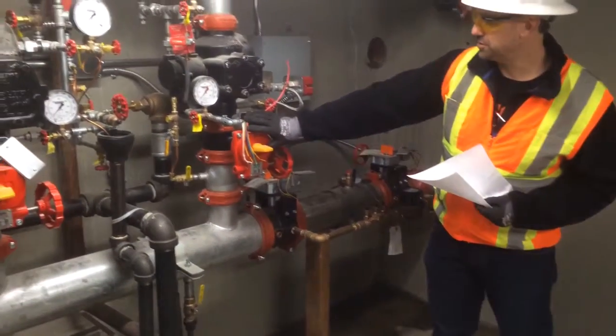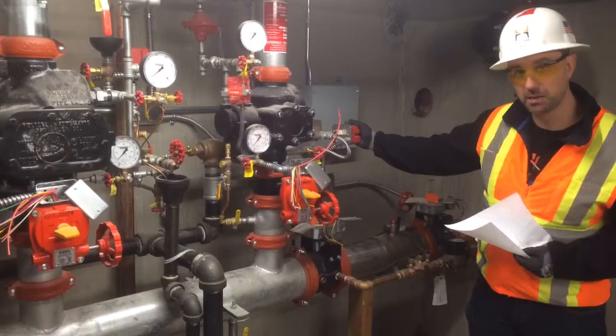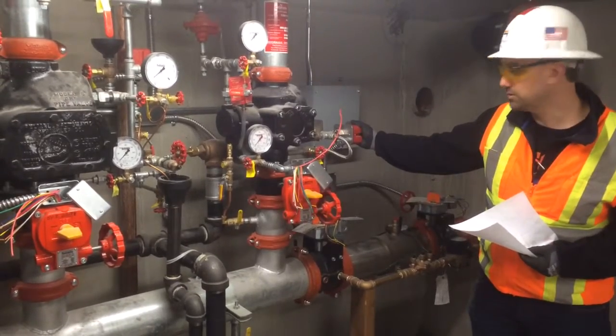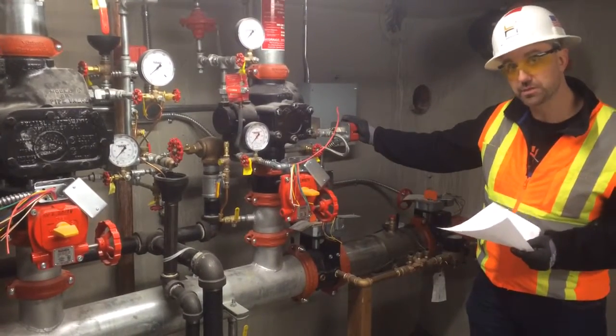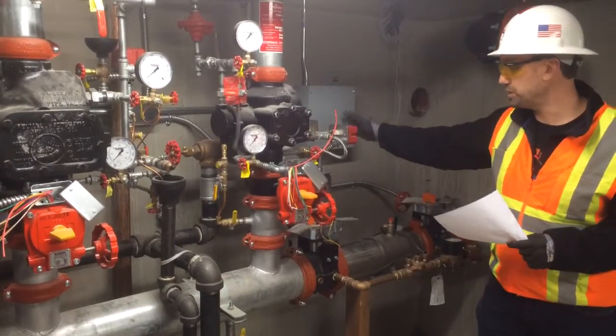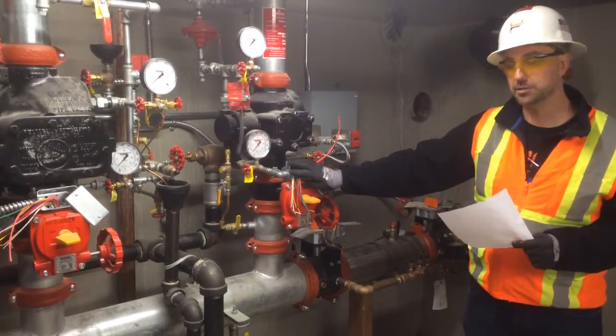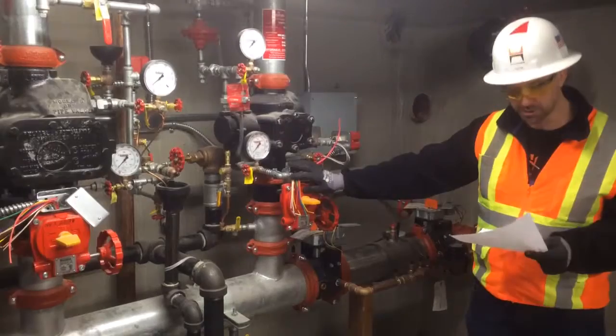We need to coordinate with the fire alarm. So each of these tamper switches and pressure switches is a point that needs to be, the drawing needs to be transmitted to the fire alarm contractor so they can show these points on their drawings and provide programming for their system to monitor this system.